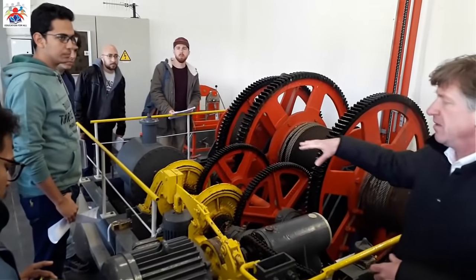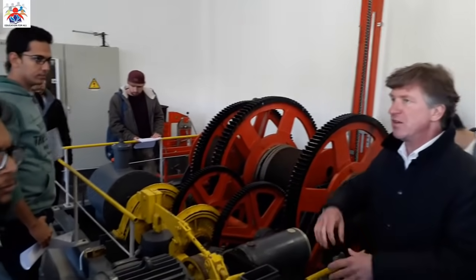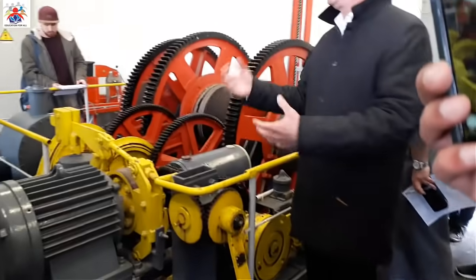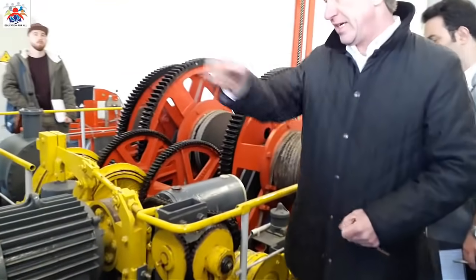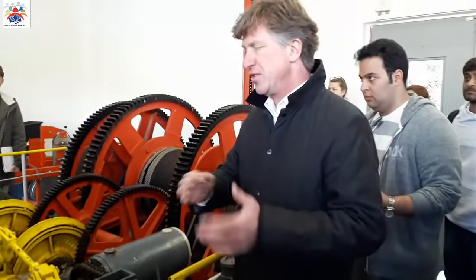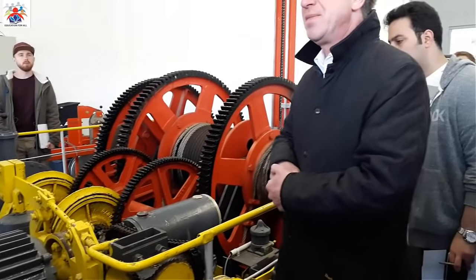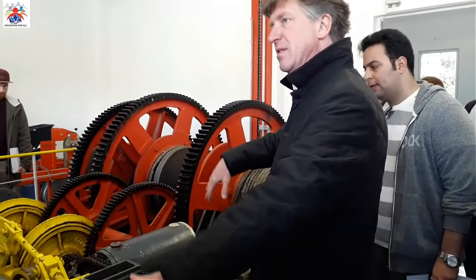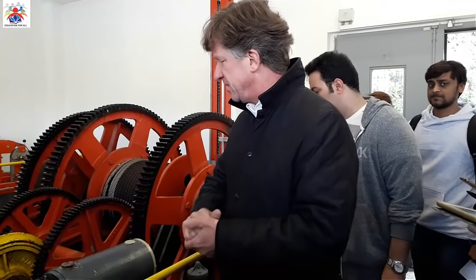For example, if the valves in the power plant are not closing, or the turbine is going through, or something happens, someone has to come up here and get this plate down for safety. And the other thing, the normal thing, would be twice a year, I think. Twice a year, I have to ask my colleague. We close this tunnel and have an inspection.